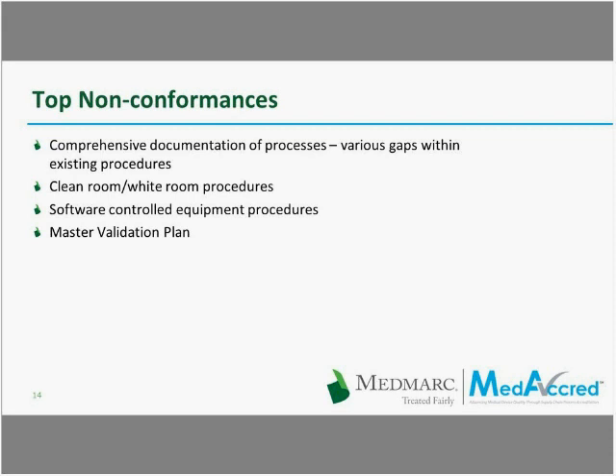Software-controlled equipment. When we talk about software-controlled equipment, in general, we're talking about robots. And a lot of facilities are using robots. What we find is that people know how to use their robots, they know how to set them up, they know how to program them, but they have not necessarily written a procedure for how that's to be done, or the procedure they have is very sketchy and really not an adequate procedure. So that's just something that people should be aware of. And last but not least, we often see an issue with the master process validation plan. We find that companies have, for one reason or another, left some gaps in this, that they haven't considered everything that they should. If you look at our audit criteria, you can see that we have a number of things that we look at for this master validation plan, but you have to have an idea of how all the products that you're making that are medical device related are covered by the master validation plan.